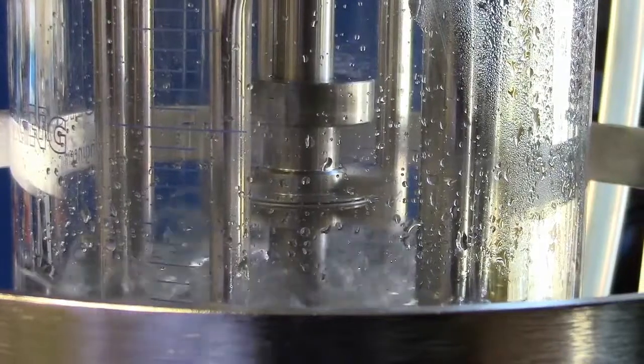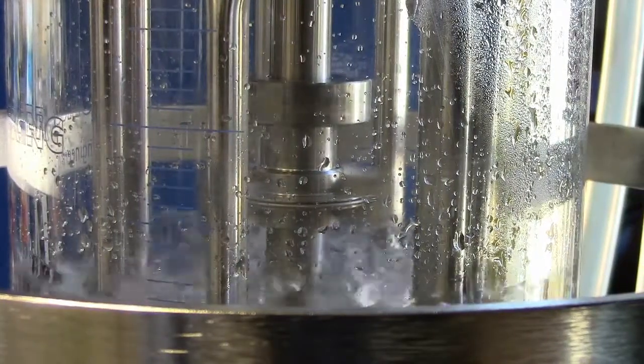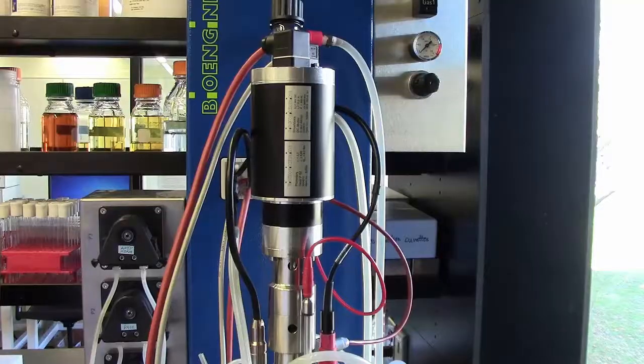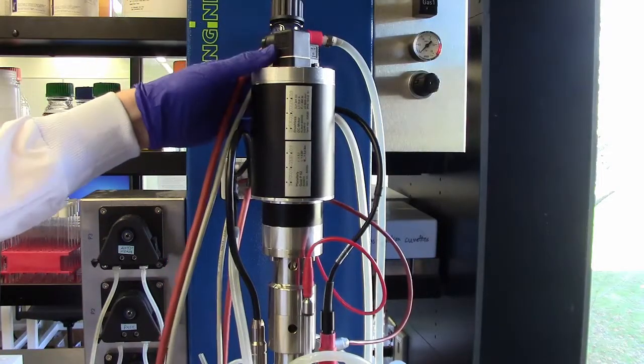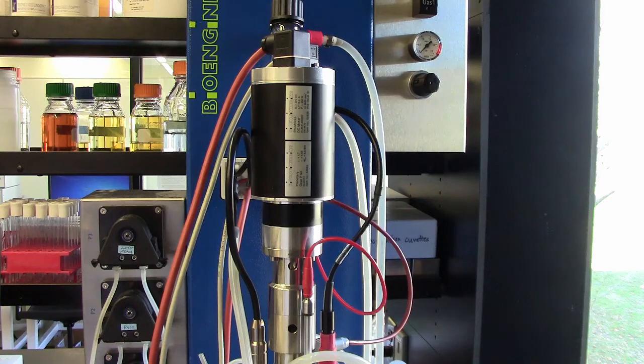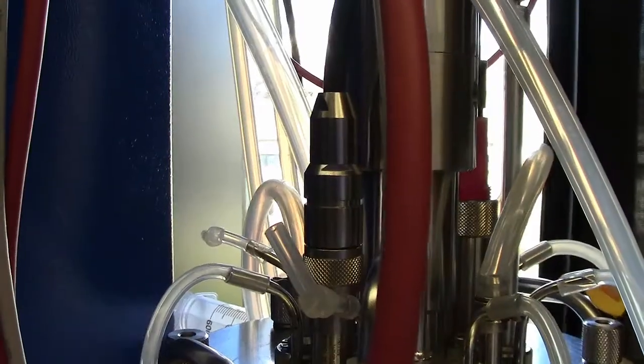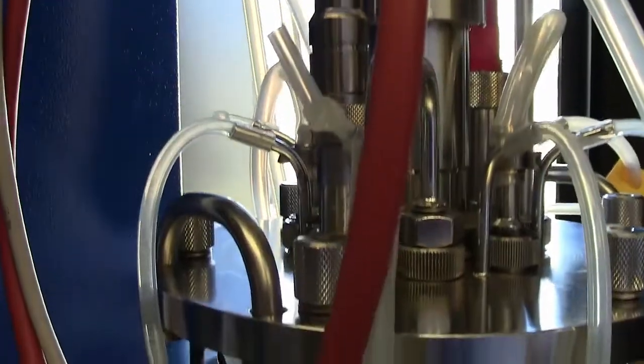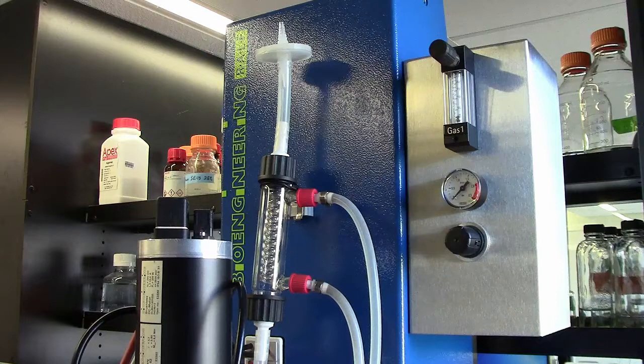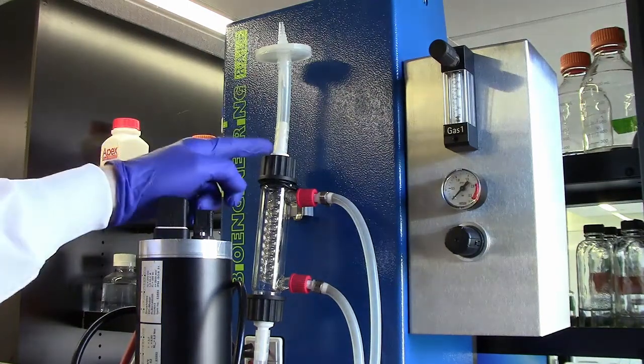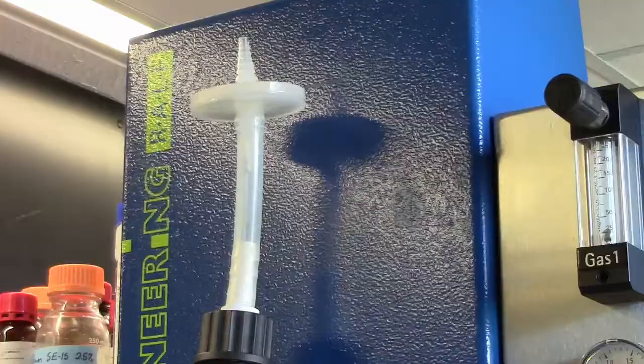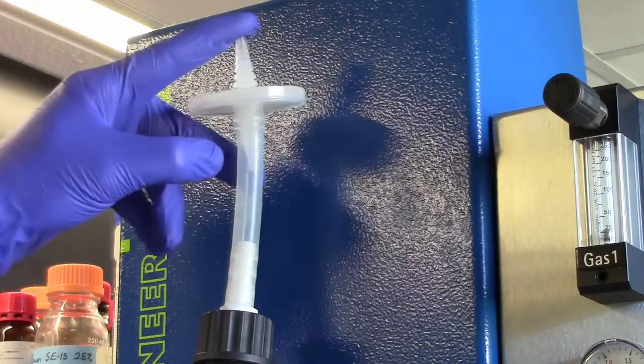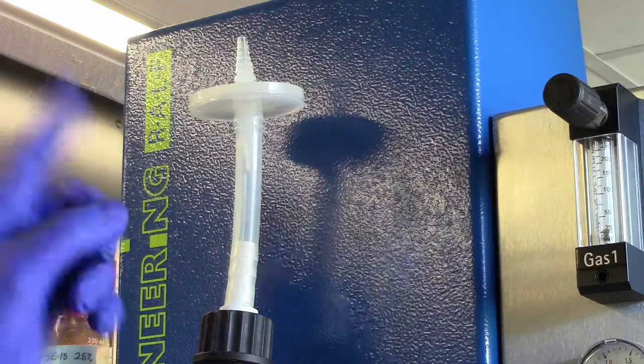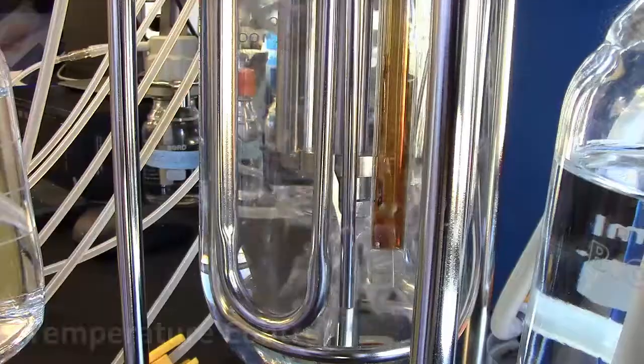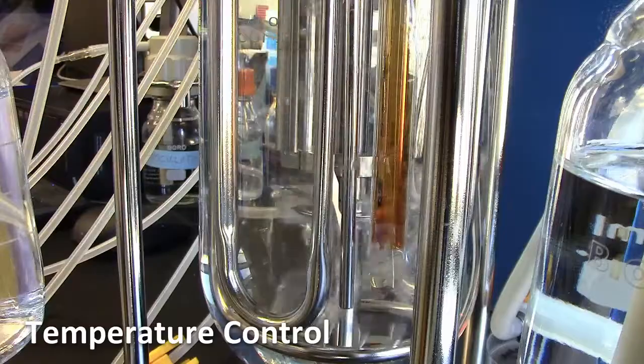The agitator in the vessel keeps the culture medium moving, providing further aeration. This is controlled by the rotary motor, the most prominent feature on the top of the vessel lid. During operation, automatic adjustment of culture aeration is measured with the O2 probe and adjusted by changing the agitator speed. Air is exhausted from the vessel through the reflux cooler, which hangs from the front of the control tower. The exhaust filter at the top of the reflux cooler must always be kept open, or pressure may build inside the fermentation vessel.